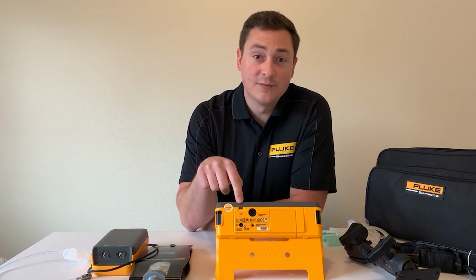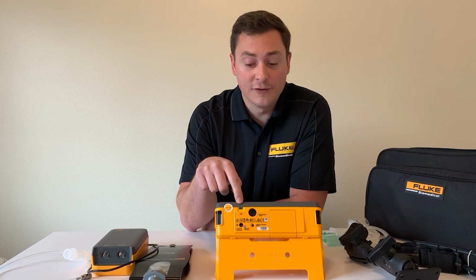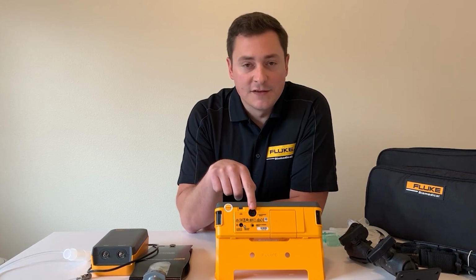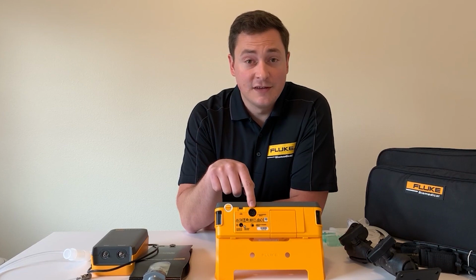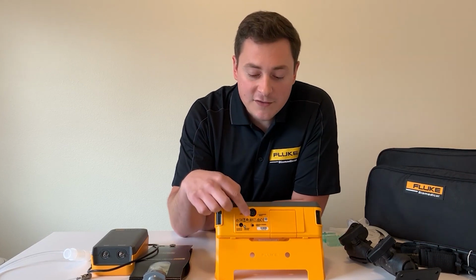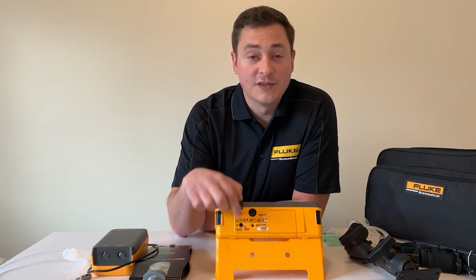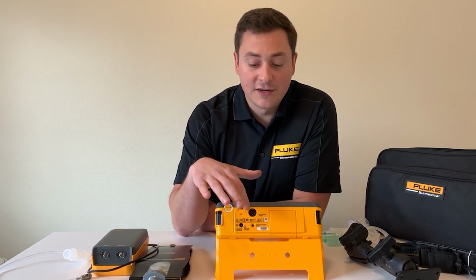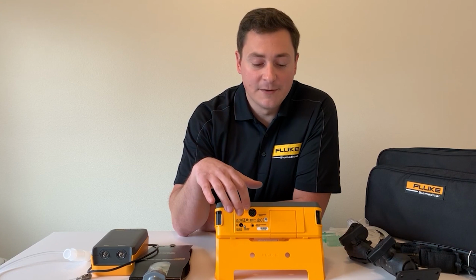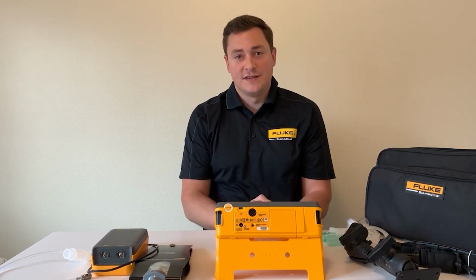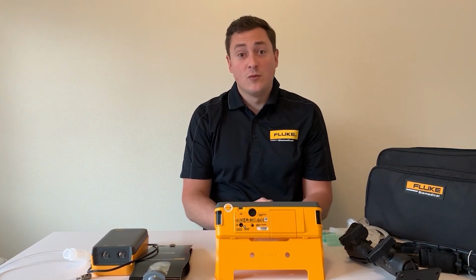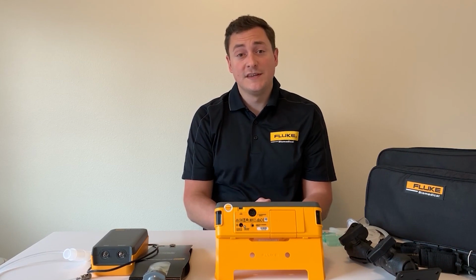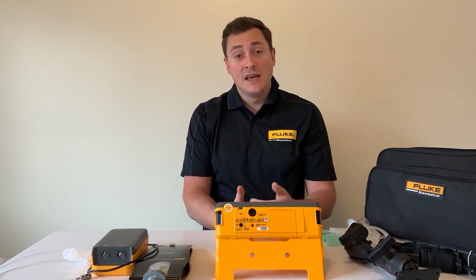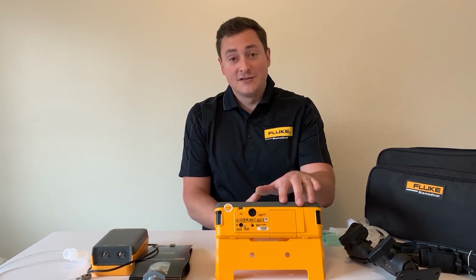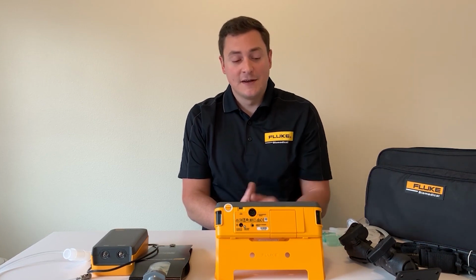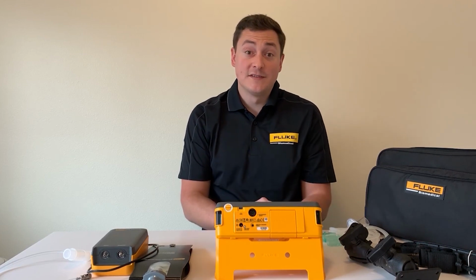You can use the Excel add-in to pull those off onto your test report or work order, and that's available on both units. There's the connection to the vapor anesthesia tester if you need to test vaporizers. There's an external TTL trigger port here, as well as power. So again, the TTL trigger and vapor are only available on the VT900A. There's also an integrated oxygen sensor. So on the VT900A, you're going to have a 1% accuracy and a 2-year life, and on the VT650, you're going to have a 2% accuracy and a 1-year life. But again, it's integrated, you can't lose it, you can't misplace it, and you only have to replace it when its lifetime is used up.